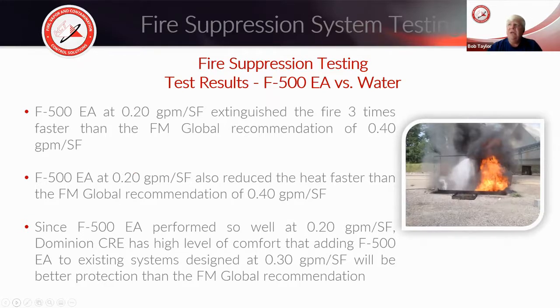So this is basically an example of some testing that was done by a third party. They used F500 on a three-dimensional liquid fire at 0.20 gallons per minute per square foot. It extinguished the fire three times faster than the recommendation that exists for water today of 0.40 gallons per minute per square foot. It reduced the heat tremendously better. It extinguished the fire, encapsulated the vapors, and it certainly is, for those that are beginning to look at what do we do to replace our AFFF or our fluoroprotein fire systems for our lubricating oil systems, it certainly makes the eyes open up saying, oh, I think I have the solution. It's called F500 encapsulator technology.